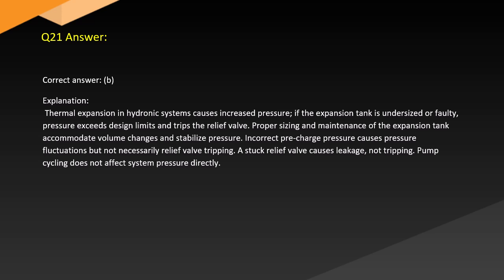Answer. Correct answer: B. Explanation. Thermal expansion in hydronic systems causes increased pressure. If the expansion tank is undersized or faulty, pressure exceeds design limits and trips the relief valve. Proper sizing and maintenance of the expansion tank accommodate volume changes and stabilize pressure. Incorrect pre-charge pressure causes pressure fluctuations but not necessarily relief valve tripping. A stuck relief valve causes leakage, not tripping. Pump cycling does not affect system pressure directly.